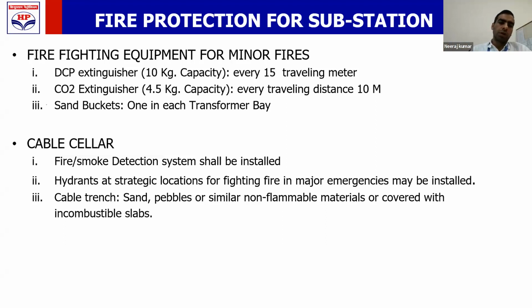Then what to do about the cable cellar? Cable cellar shall be provided with the smoke detection system as provided in the substation. In addition to that, hydrants, which are not used in the substation, may be provided in the cable cellar to fight a major emergency if one arises in the cable cellar. The word used in the standard is may, meaning it is not made compulsory.